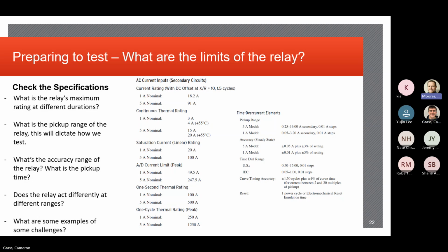So here's an example. In a time overcurrent application, you have a pickup value and then you have a time test value, right? So the minimum pickup you would use a spare output for. Say the minimum pickup is 1 amp. That's when the relay will start timing when it sees 1 amp and above. Then it uses the curve, the timing curve, and the time dial and the tap and all that stuff. The tap is part of the minimum pickup, but that timed out element will be in the trip string. So we would want to monitor the trip string. So you understand the difference.